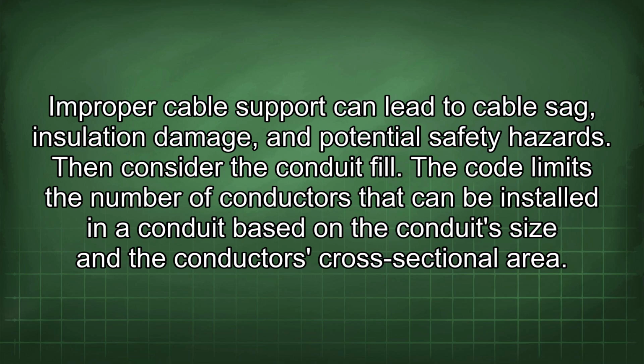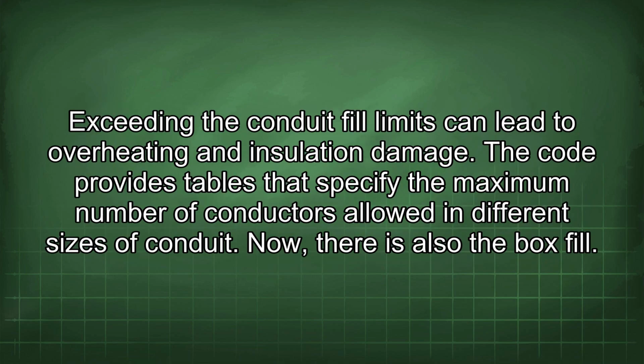Then consider the conduit fill. The code limits the number of conductors that can be installed in a conduit based on the conduit size and the conductor's cross-sectional area. Exceeding the conduit fill limits can lead to overheating and insulation damage. The code provides tables that specify the maximum number of conductors allowed in different sizes of conduit.